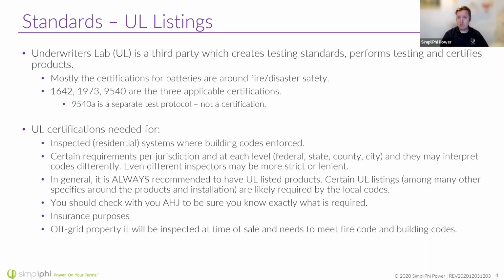I could spend this whole hour just talking about the 9540A testing, but essentially, the cell did go into thermal runaway. It spread a little to adjacent cells, but it didn't start a self-propagating fire inside the battery. The battery didn't spread to other batteries, and it didn't spread outside the cabinet into the test chamber, which would represent the homeowner's garage. So it was a nice proof in the pudding showing how safe one of these systems can be, even when forced into thermal runaway.